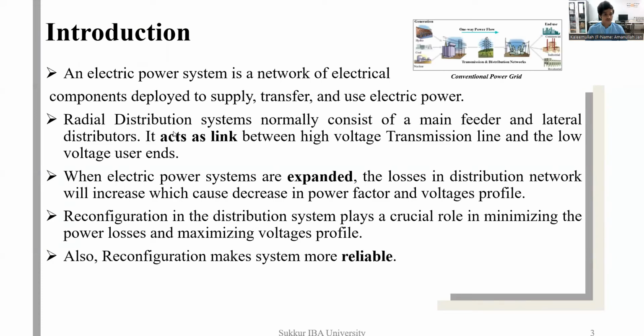So moving towards the introduction. An electric power system is a network of electrical components deployed to supply, transfer, and use electric power. A radial distribution system normally consists of main feeders and lateral distributors. It acts as a bridge between the high voltage transmission line and the low voltage user ends. When electric power systems are expanded, the losses in the distribution network increase, which causes a decrease in power factor and voltage profile. Reconfiguration in the distribution system plays a vital role in minimizing the power losses and maximizing the voltage profile. Also, reconfiguration makes the system more reliable.